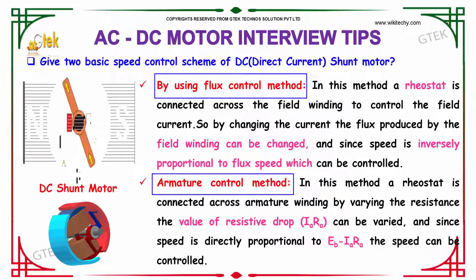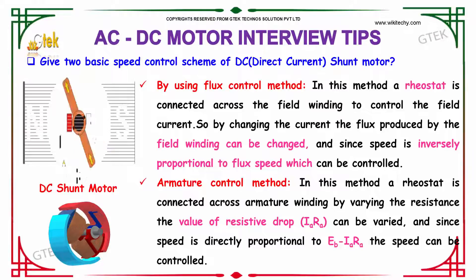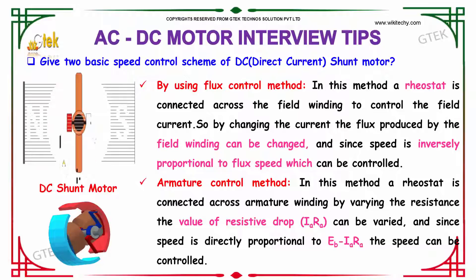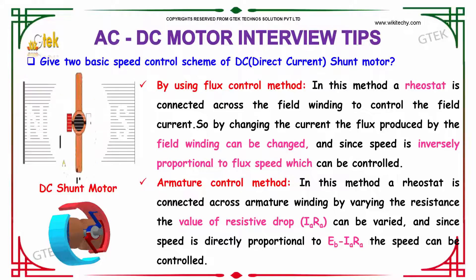By using the flux control method, a rheostat is connected across the field winding to control the field current. By changing the current, the flux produced by the field winding can be changed, and since the speed is inversely proportional to the flux, speed can be controlled.